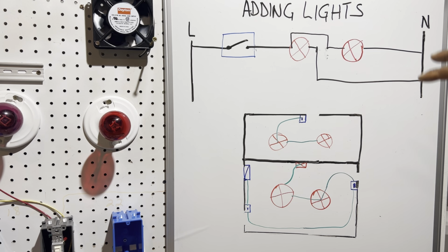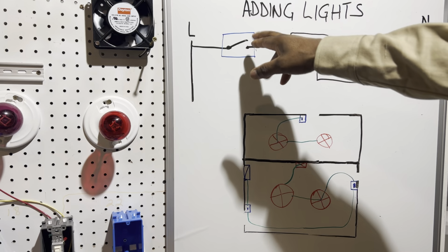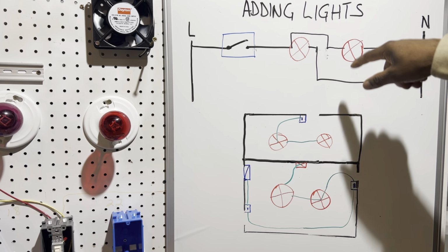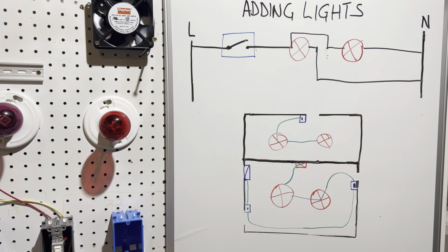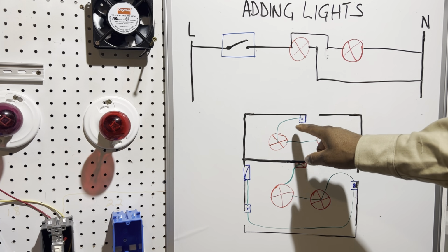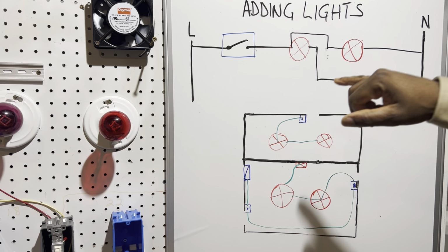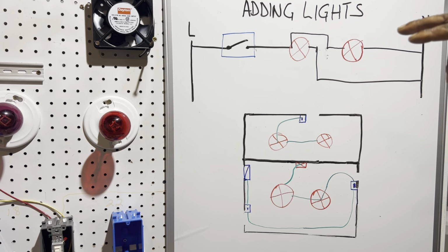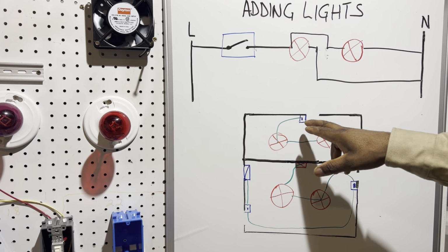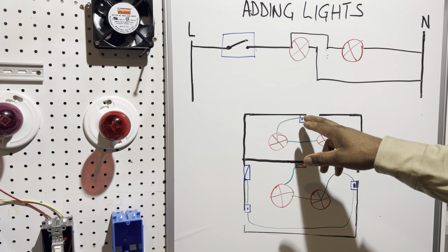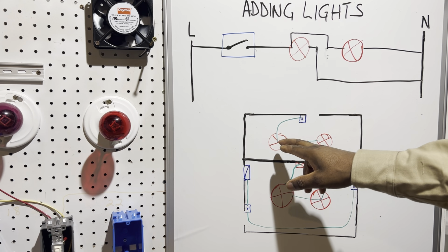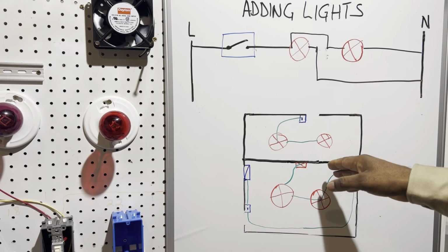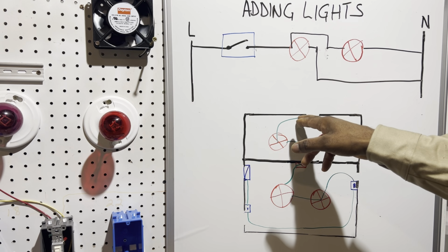So that's your schematic right there. So when you turn on the switch, that light will turn on, that light will turn on, because you got both live and neutral. But if you had to go to the switch, you could be disappointed. But just for a single switch only, if you see a single wire running from a switch going to the light and it doesn't go share to another light, you are likely to find a neutral in the switch.